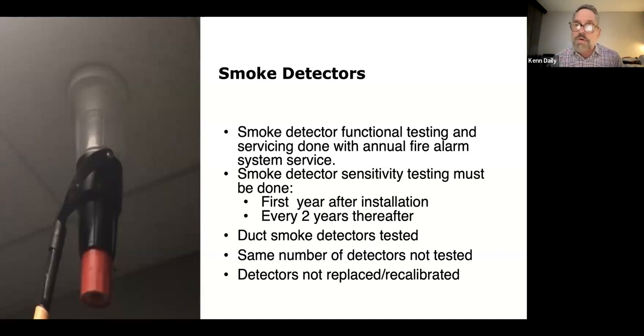So if 0 to 4 is the expected range, obviously 9 is too high, and let's say 0.5 would be too low. So either over or under sensitivity, and that doesn't pass. So then you have to either recalibrate it, clean it, or replace it. Some of you listening, I would tell you to go back and look at your sensitivity report you had done recently, the most recent one. And I would tell you, some of you have the same sensitivity number for every one of your devices in your building. And I have a serious problem with that.